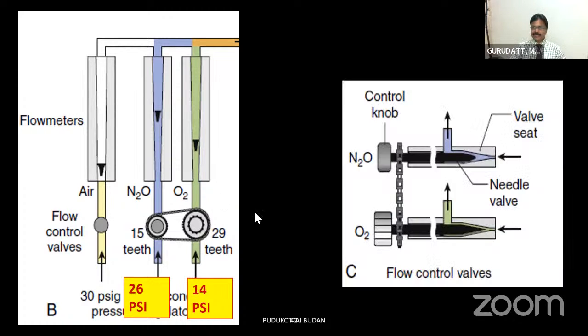Another thing you should always know is that the nitrous oxide needle valve has less taper, whereas the oxygen needle valve has more taper. That means the amount of oxygen entering the flow meter itself is slightly less when compared to the amount of nitrous oxide entering the flow meter. So that's how the 3:1 ratio between nitrous oxide and oxygen is completed. That means the minimum oxygen you can always give is 25%.